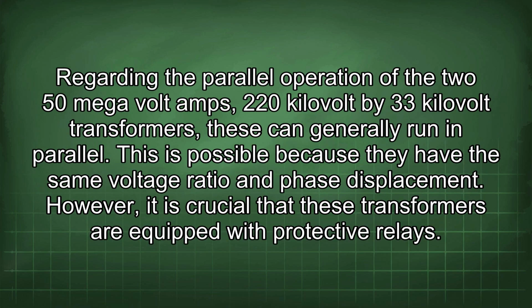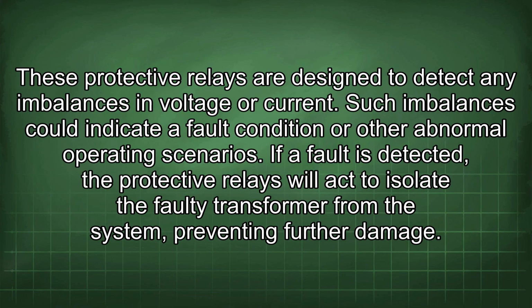Regarding the parallel operation of the two 50 MVA, 220 kV by 33 kV transformers, these can generally run in parallel. This is possible because they have the same voltage ratio and phase displacement. However, it is crucial that these transformers are equipped with protective relays. These protective relays are designed to detect any imbalances in voltage or current. Such imbalances could indicate a fault condition or other abnormal operating scenarios.